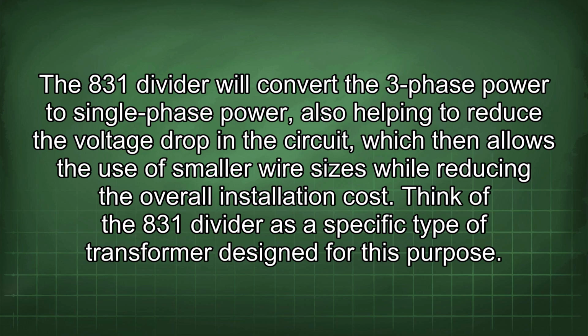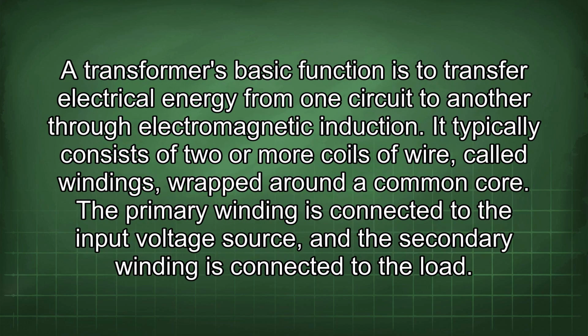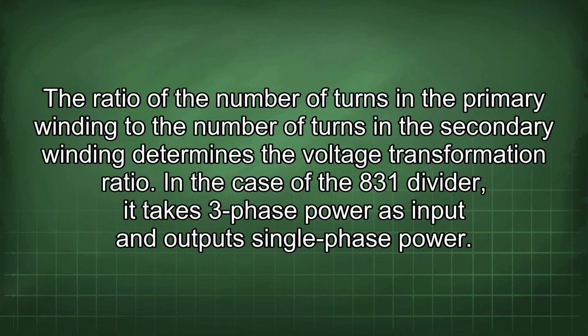Think of the 831 divider as a specific type of transformer designed for this purpose. A transformer's basic function is to transfer electrical energy from one circuit to another through electromagnetic induction. It typically consists of two or more coils of wire, called windings, wrapped around a common core. The primary winding is connected to the input voltage source, and the secondary winding is connected to the load. The ratio of the number of turns in the primary winding to the number of turns in the secondary winding determines the voltage transformation ratio. In the case of the 831 divider, it takes three-phase power as input and outputs single-phase power.